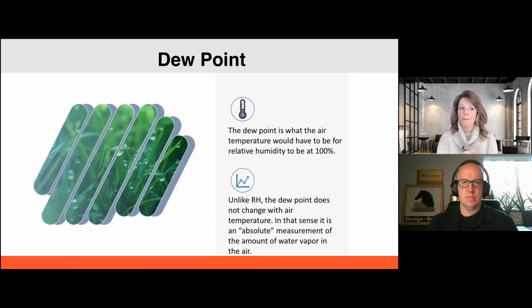So the dew point basically is, if you can look outside in the spring, summer, and fall and see green grass, you're what we call living in a green grass climate. And when you look outside in the morning and there's dew on the grass, that means that the air temperature has hit dew point. And we need to really get the trades and homeowners to understand dew point, because there are situations, especially with our air conditioners now, where we have the opportunity to do some overcooling to try to remove a little bit more water, but we have to be careful that we don't have places in the house that can hit dew point. So if the register starts dripping water, the air's gotten too cold trying to remove more moisture and we've hit dew point.